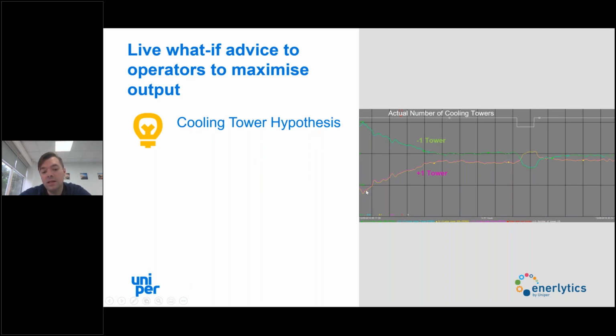And the bottom line is the pink-yellow one, that's saying what would happen to the efficiency and output if I added a cooling tower. All of this is normalized for operating condition and ambient conditions, and the target is to get it on this black line here. And it's for a 24-hour period. So you can see that in the morning, the operator should be taking out a cooling tower in its operation. And if they took that out, they would gain 0.05%.